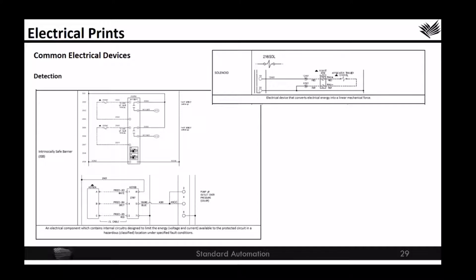We also have solenoids. Solenoids are electrical devices that convert electrical energy into a linear mechanical force. Generally, the way that standard automation uses solenoids is that it converts an electrical signal into an air signal, and we use that air signal to pilot valves. And so our solenoids convert the electrical signal into the mechanical air signal.